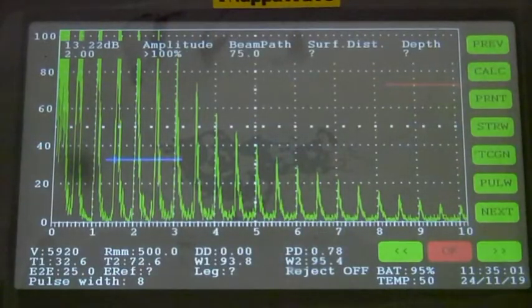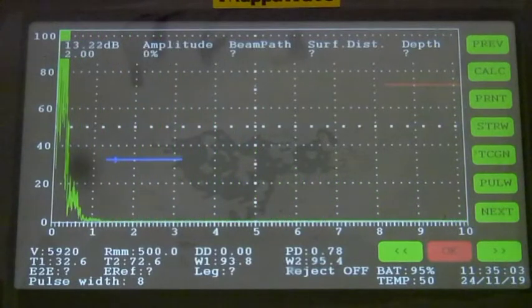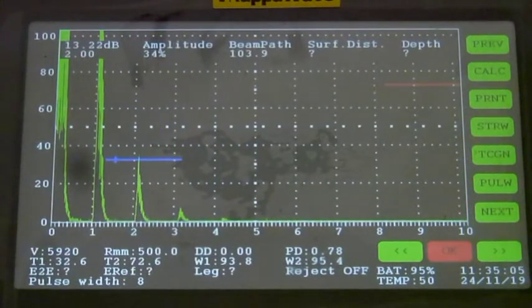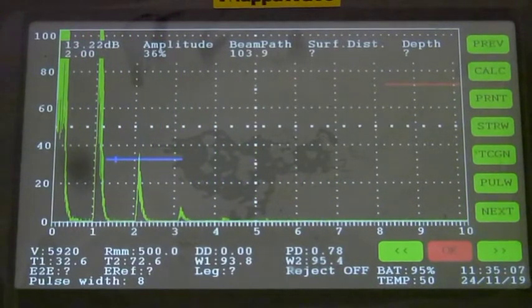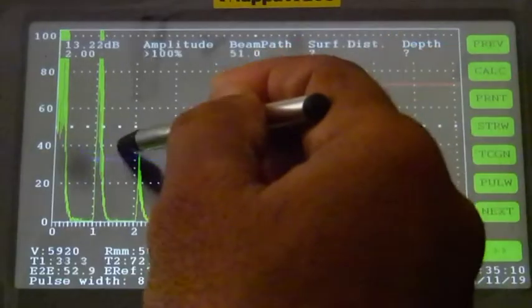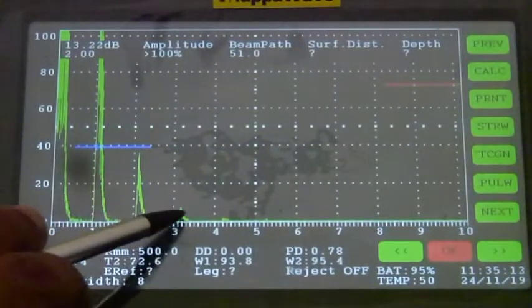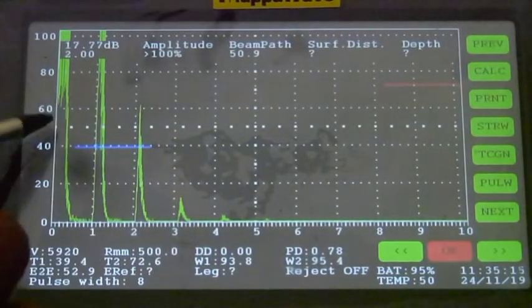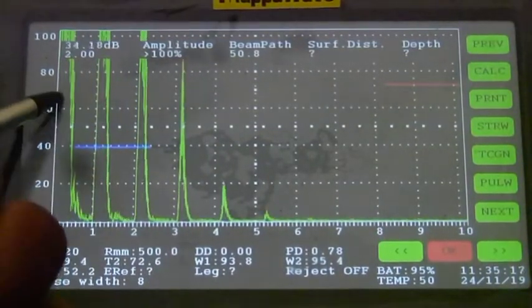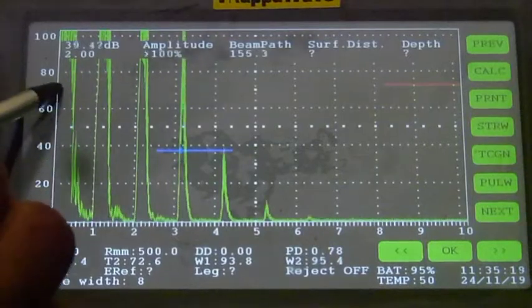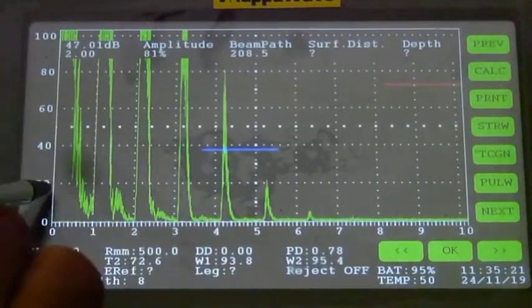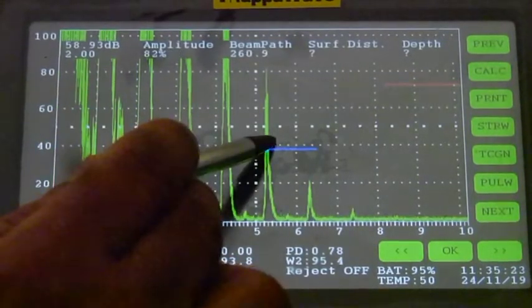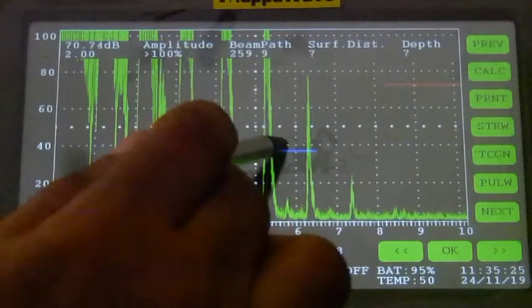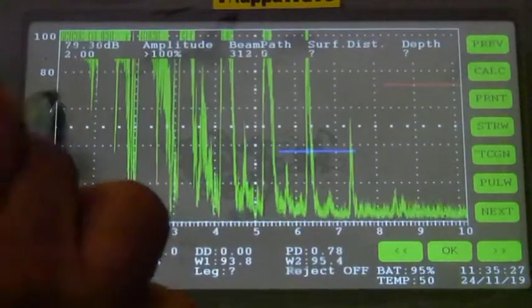Here the penetrative power of the unit is checked. A 500 millimeter range is calibrated and a 2 MHz probe is actually used. When placed on a perspex insert on the V1 block, you have these backwall echoes. You have something like 1, 2, 3, 4, 5. Okay, so that's the 7th backwall echo in place.